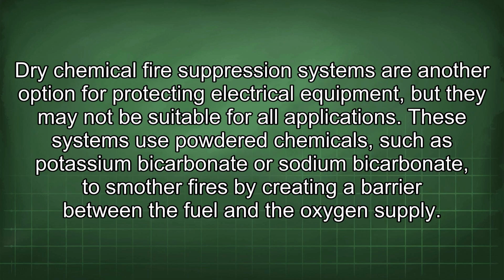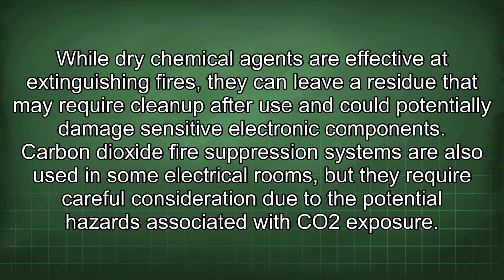Dry chemical fire suppression systems are another option for protecting electrical equipment, but they may not be suitable for all applications. These systems use powdered chemicals such as potassium bicarbonate or sodium bicarbonate to smother fires by creating a barrier between the fuel and the oxygen supply. While dry chemical agents are effective at extinguishing fires, they can leave a residue that may require cleanup after use and could potentially damage sensitive electronic components.